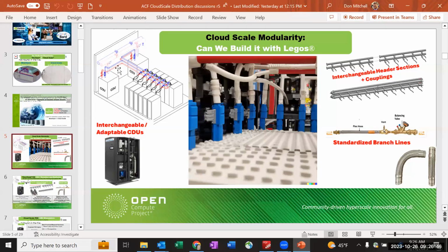But if it's a colo, and it's all connected to a common rear door heat exchanger or something, and somebody goes in there with a new server design that's got a microchannel cold plate, then it's a least-common-denominator situation. That's what's going to drive the coolant quality. Somebody drops that thing in there, and all of a sudden he needs 25 micron filtered coolant, otherwise you'll clog the microchannels.